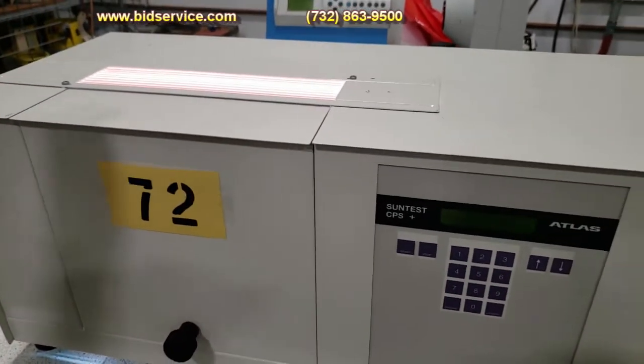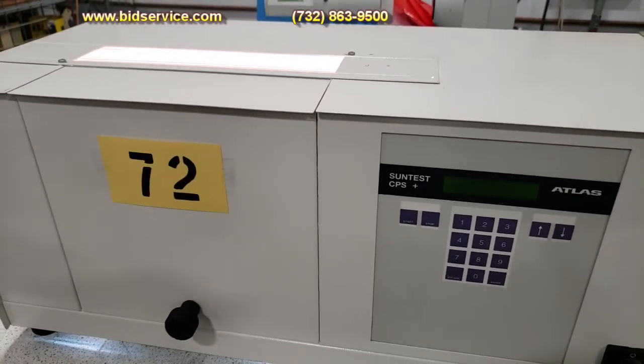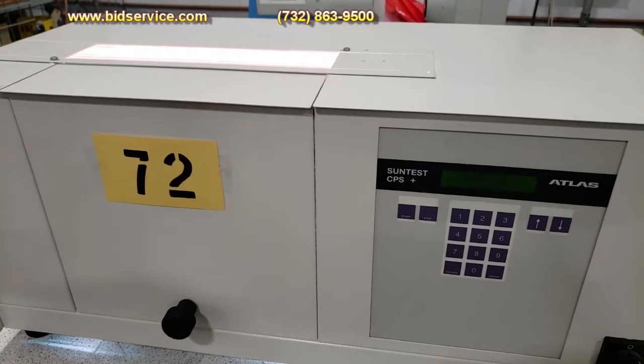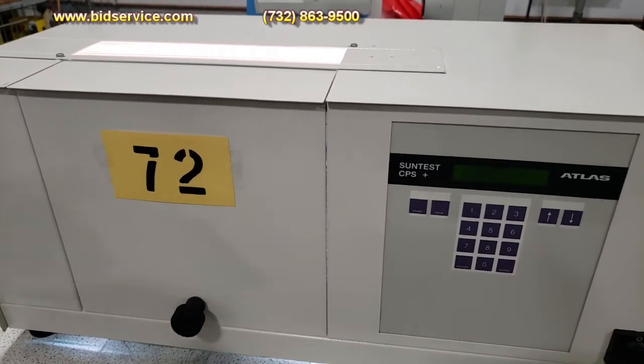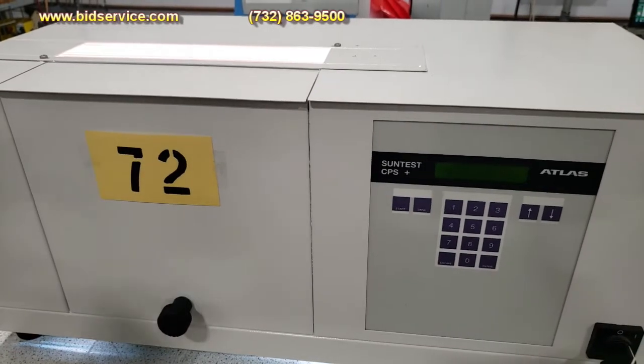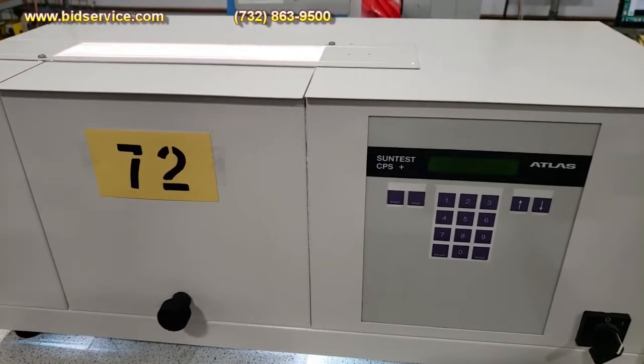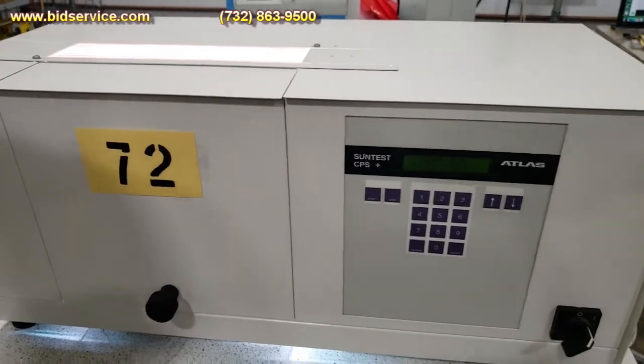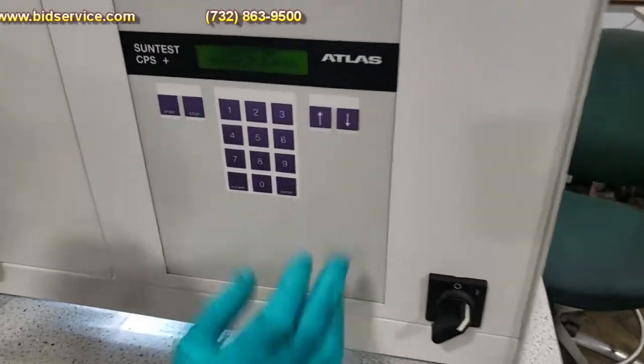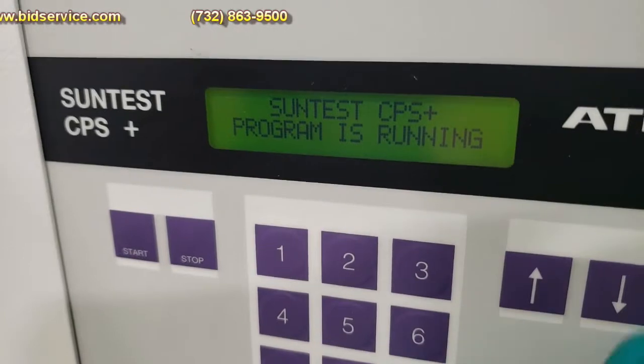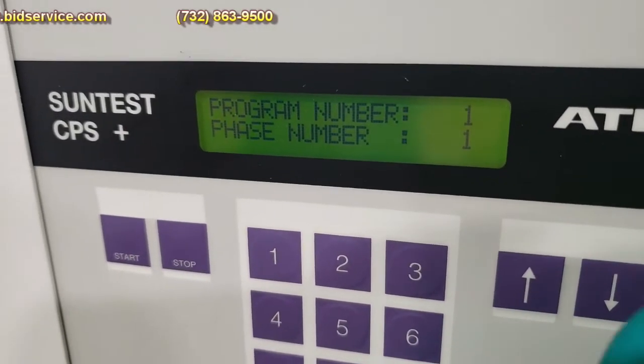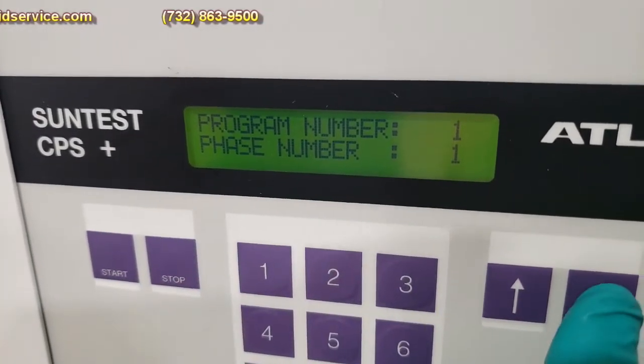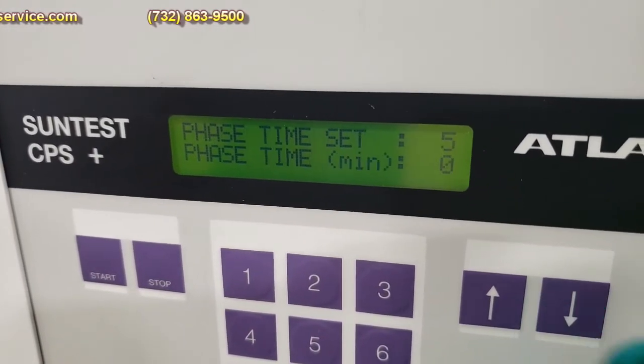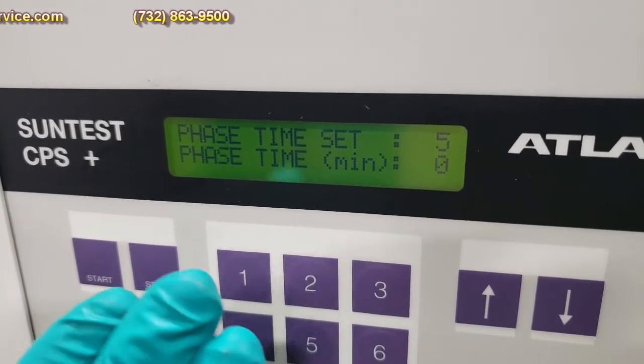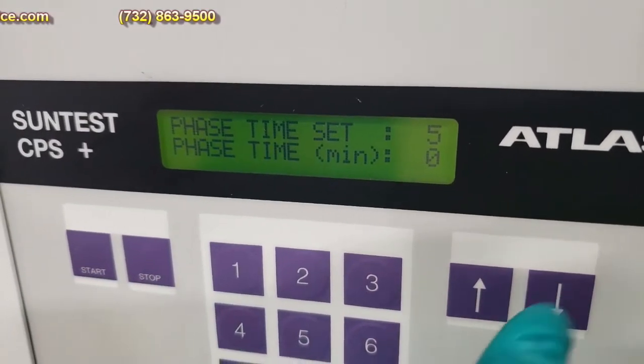Now, as far as determining the calibration for the irradiance, you'll need to get a meter. There's no meter provided with the system, but it is an option. Through Atlas, you'll be able to pick that meter up, and you can actually have that installed inside while you're doing a calibration on the lamp. But for right now, if you look at the screen here, it just shows that the program is running. I believe if you step down, you can see that phase 1 is in process right now, program 1. I think this program is running 2 phases at 5 minutes each.